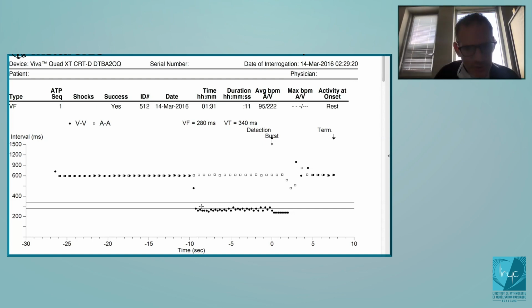And since the VF cycles do not increment the VT counter, there is going to be a long delay. You will need to wait a lot before filling the VT counter. And if there is an oscillation, you probably want to treat it more like a VF than a VT.